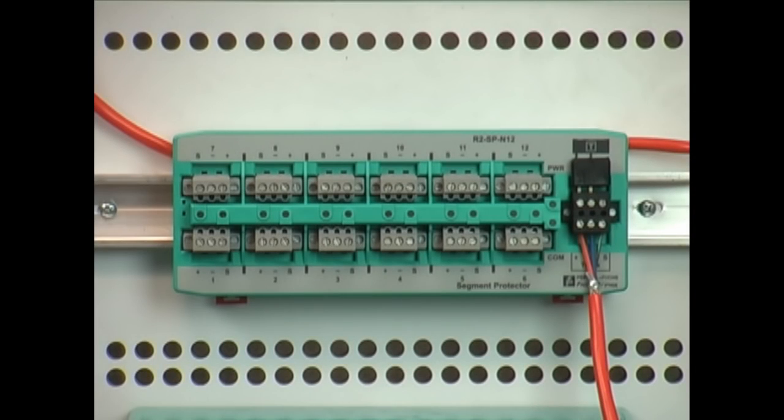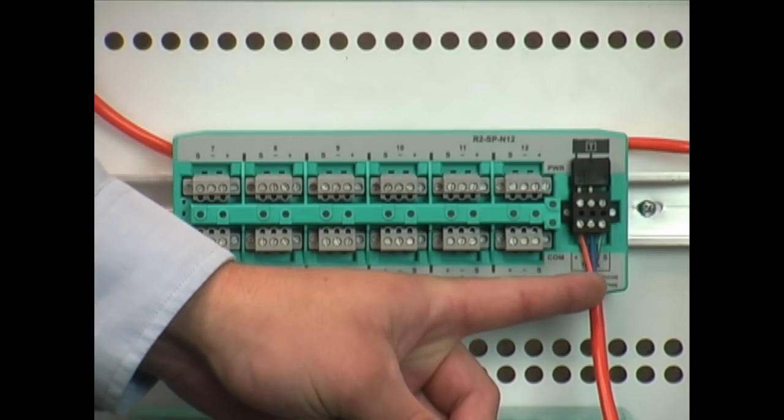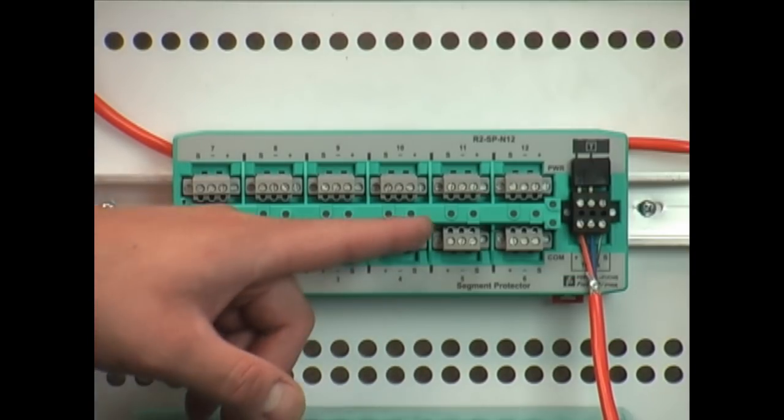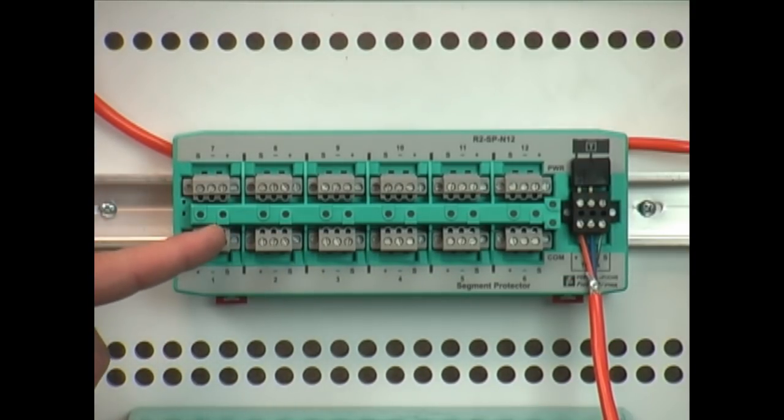The next component for a Foundation Fieldbus segment is going to be some sort of field distribution and for Pepperl+Fuchs we call that a segment protector. This is what takes a trunk in connection from your power supplies and converts that into different spur connections for your individual field devices.